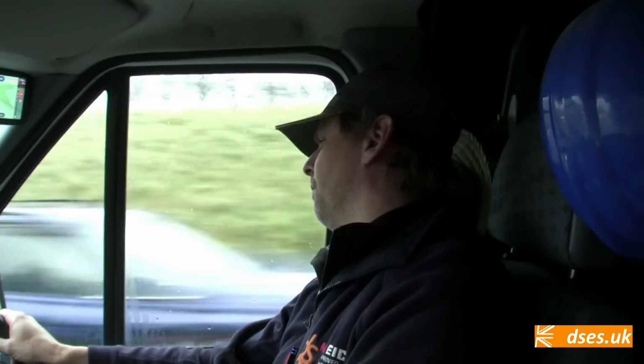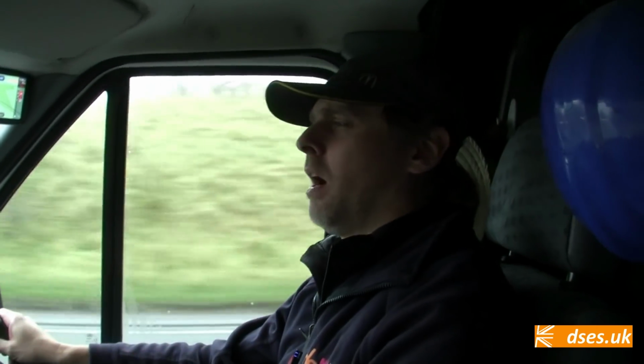And that's because the inspection may highlight things that need remedial work, or some kind of workaround because something's not quite right, like breaks in the ring or something like that, something that's got to be sorted or worked around. So it's quite hard to turn up with a consumer unit under your arm and all the necessary protective devices for a job that you haven't tested and inspected, or even in this case seen. We've never been here before, so goodness knows what we've got here.